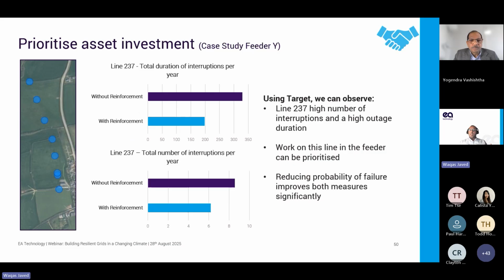If you look at line 237, it is an overhead line running across agricultural land, supplying a small dispersed settlement. The data available didn't include the specific cause of faults, so we didn't know, for instance, if the primary issues were vegetation, pole condition, or conductor damage. That's where local engineering knowledge would typically provide critical insight. But even without those details, the target model allowed us to simulate a reinforcement scenario, where the probability of failure was reduced through some form of targeted intervention, for example tree cutting, circuit upgrade, or automation.